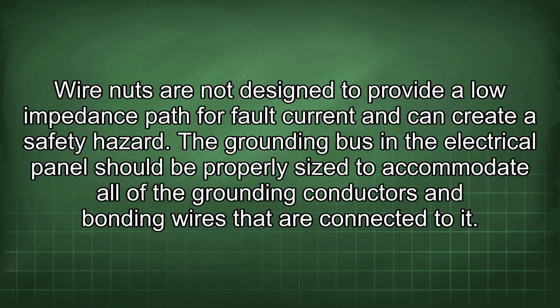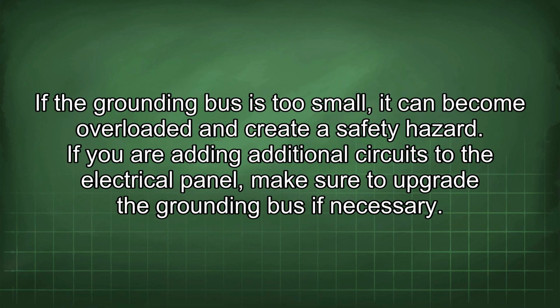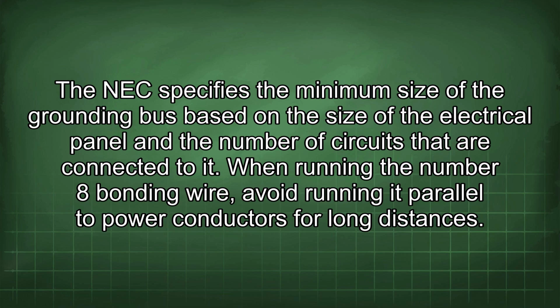The grounding bus in the electrical panel should be properly sized to accommodate all of the grounding conductors and bonding wires that are connected to it. If the grounding bus is too small, it can become overloaded and create a safety hazard. If you are adding additional circuits to the electrical panel, make sure to upgrade the grounding bus if necessary. The NEC specifies the minimum size of the grounding bus based on the size of the electrical panel and the number of circuits that are connected to it.